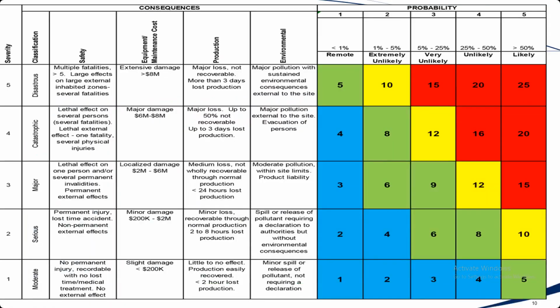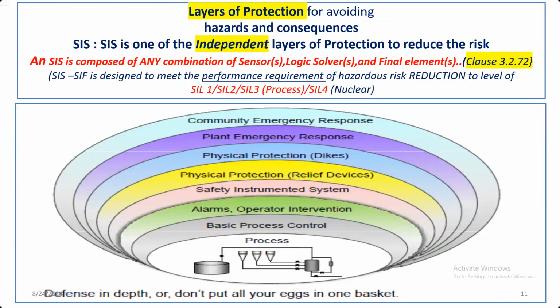Now this is a risk matrix. Now risk is not only for safety, it can be for equipment, it can be for production loss, it can be for environment. So these are all the consequences. 4 types of consequences are described here, and probability of happening, likely, unlikely, very likely, extremely likely, are shown in this risk matrix. One would like to work in the yellow region or green region. But risk needs to be classified, and this risk classification is done after the HAZOP.